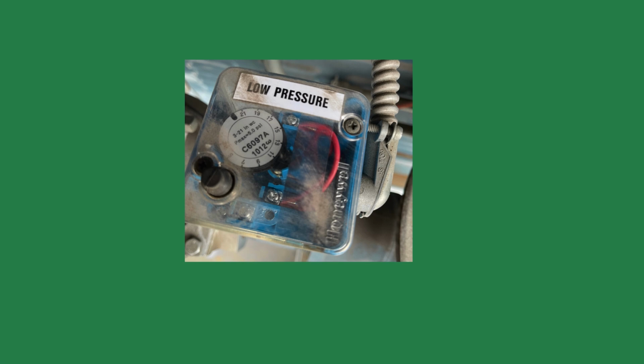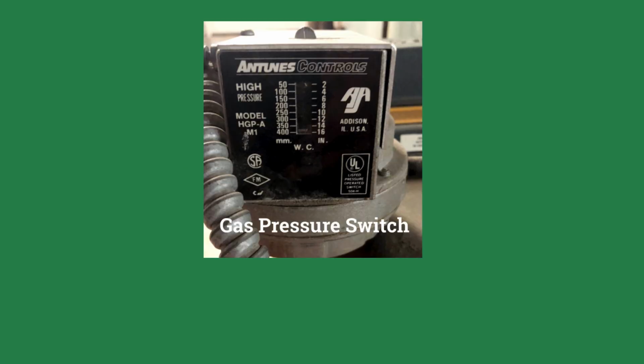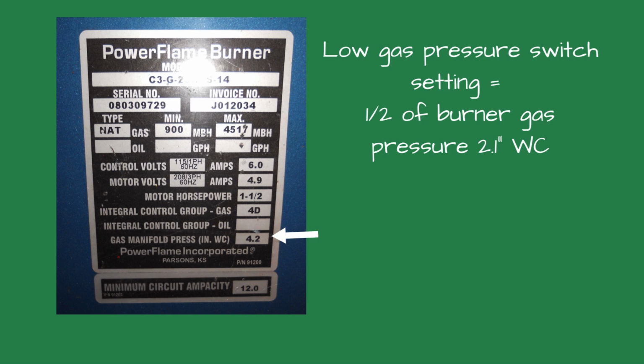off and won't restart until the reset button is pushed and the gas pressure in the gas train is above the set point. If the gas pressure is higher than the high gas pressure switch set point, it again will shut off the burner and won't start until the pressure drops below the set point and the manual reset button is pushed. So what should we set these pressure switches for?